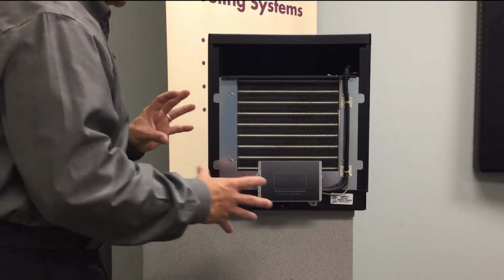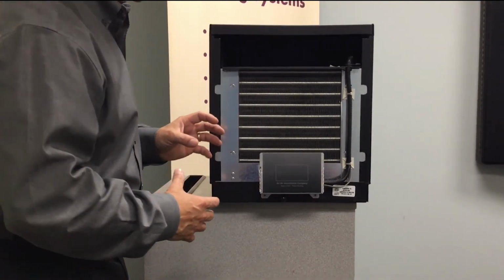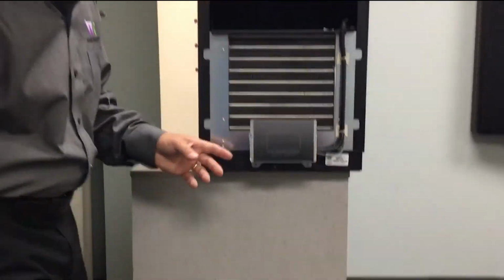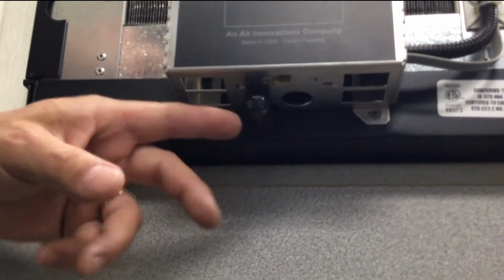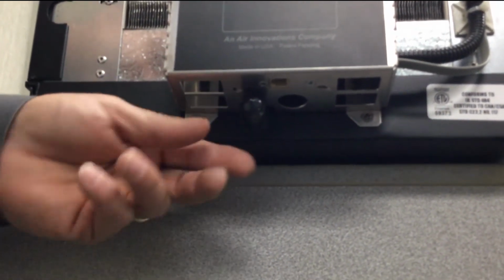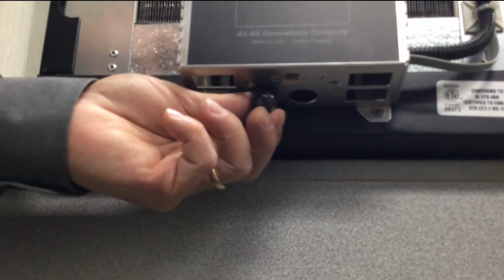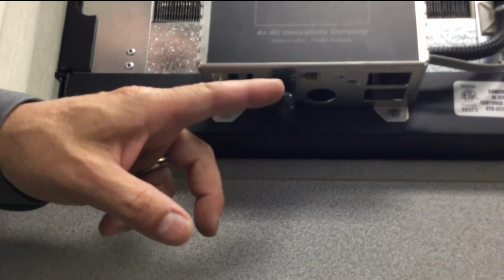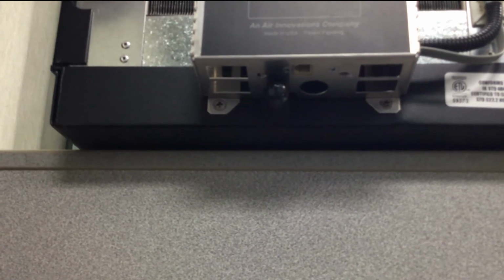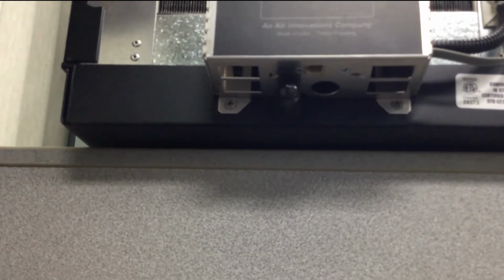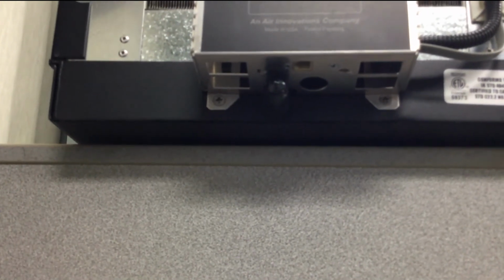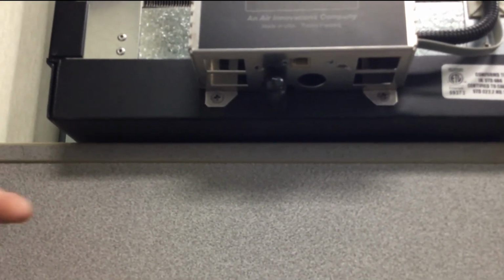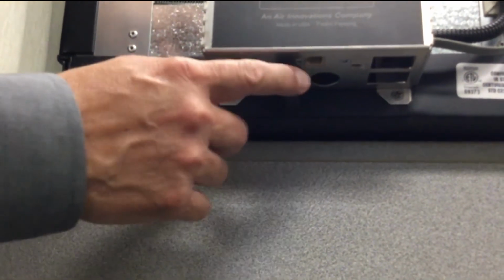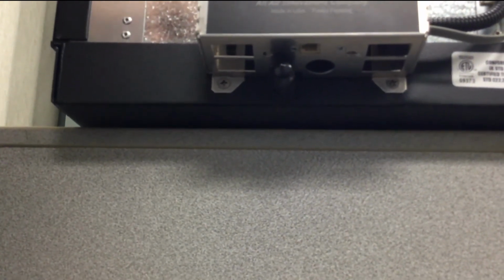A couple things to point out on this section is this is where the drain overflow is at the bottom of the unit. So you can see we've got a cap on it right here, and it usually ships from our factory open. So you'll have an open tube coming out of the bottom of the unit, and we ship to you this cap as a separate piece that can be added if you find that you're not getting any moisture out of the system, that it's not draining, and that you've got no extra condensation issues. So that can be placed on that overflow drain.